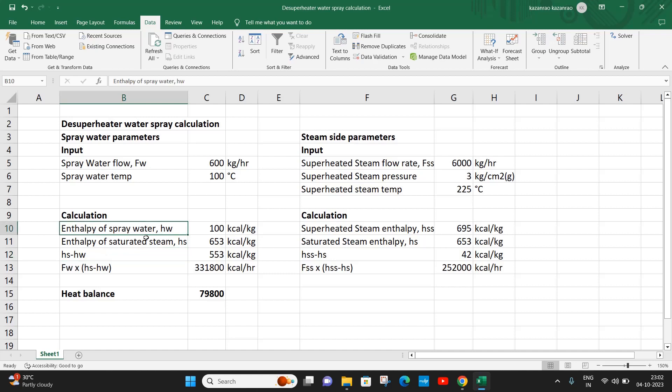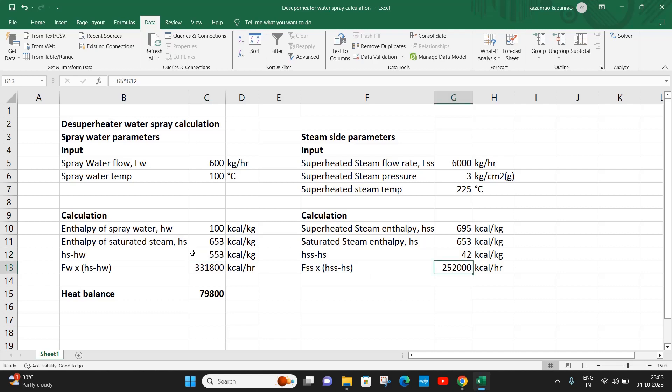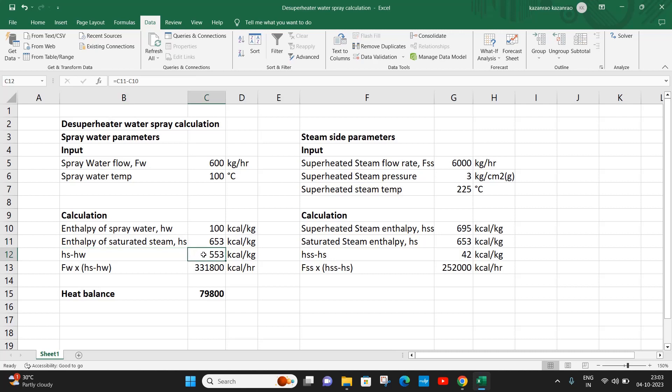The difference between enthalpy of saturated steam and the spray water is 553. So for every one kg of spray water that we mix into the system, we have only 553 kilocalories that can be transferred from superheated steam to the water, because this water cannot cross the saturated steam enthalpy. Since we cannot cross 653 kcal per kg, the amount of heat that can be absorbed per every one kg of water sprayed into the system is 553. As per heat balance...